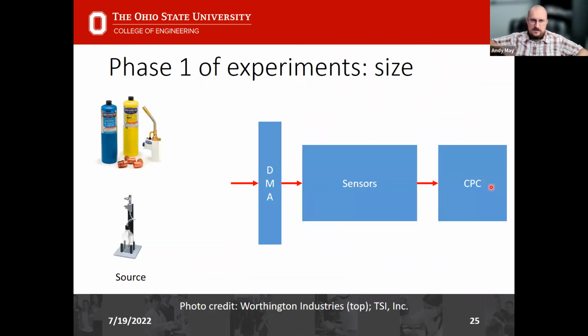And so finally, moving on to some of the work that's actually in the paper. In phase 1 of our experiments, we're looking at the effect of particle size. And so here we generated two types of particles. We modified a propane torch so it burned less efficiently and produced a lot of soot. And we also atomized some ammonium sulfate solution. For both of these sources, we then passed those particles through a DMA so we could select a given size. We introduced the size selected particles into a chamber containing our sensors. And we measured the number concentration in that chamber using a CPC.